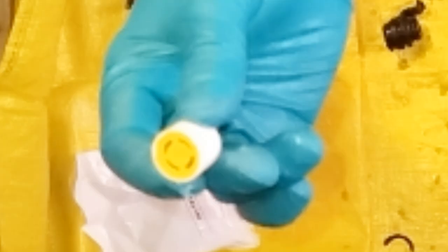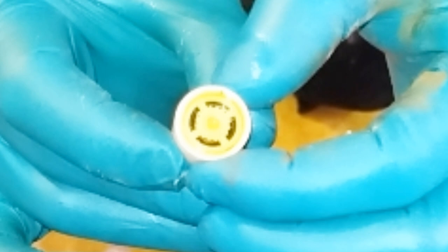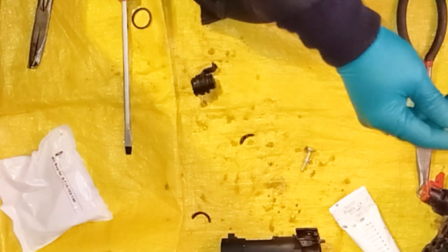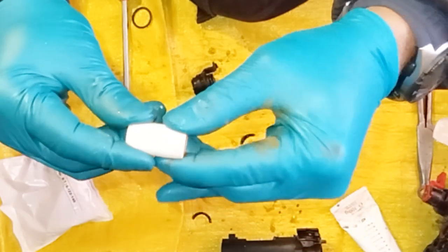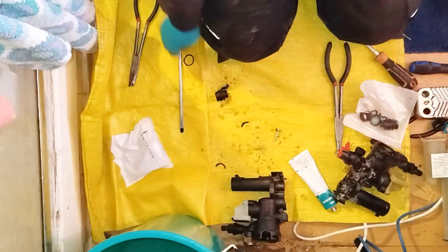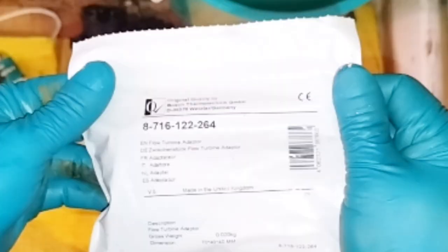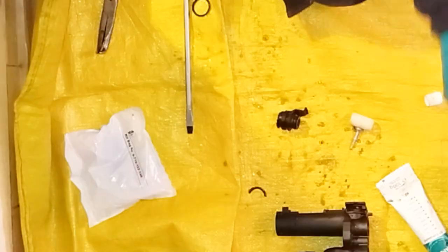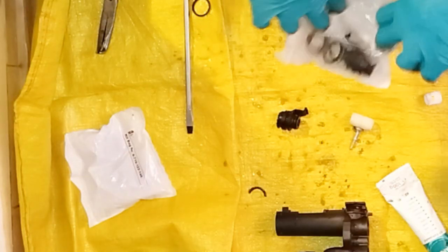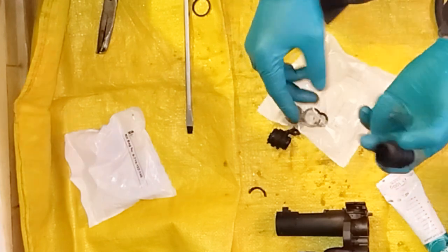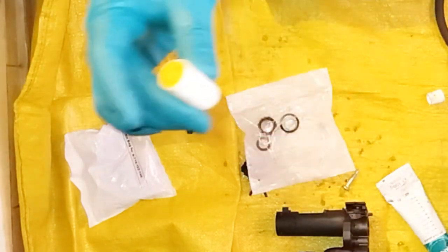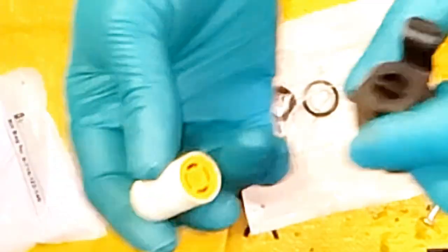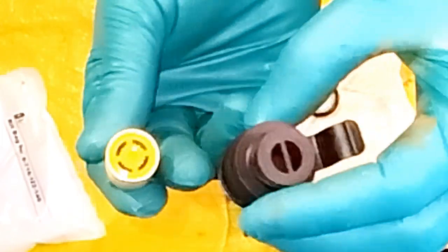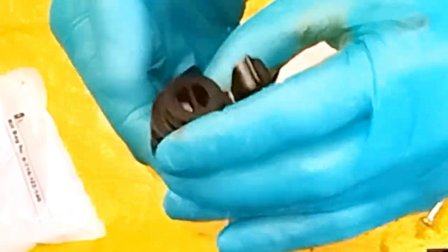So this is the flow restrictor, which adjusts the flow according to the size of the boiler, so the hot water is correctly adjusted and comes out as the boiler can cope with. So this is the new flow turbine adapter. This is the part number for the new one. So we'll remove it from the packaging, and there are O-rings which need to go on this one. Obviously, we'll put the flow restrictors back in this direction. So you can see the yellow one is visible from the side where there is no nut.